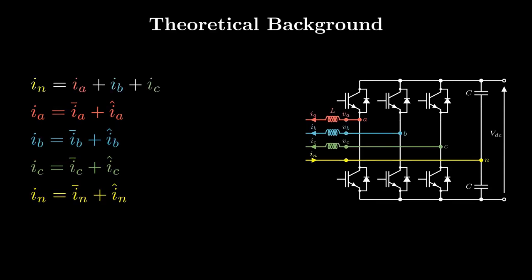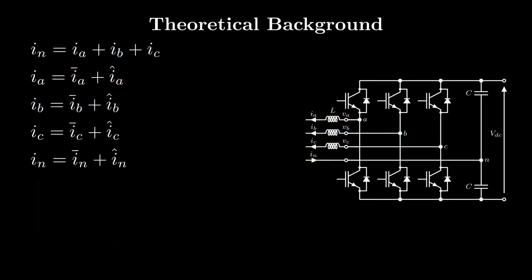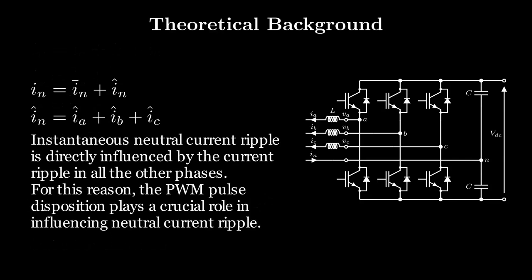The neutral current is given by the sum of phase currents, and any of these currents can be split into two parts. The first one is the AC component, having sinusoidal waveform. The second one is the switching current ripple caused by PWM high-frequency component. Therefore, neutral current ripple can be seen as the instance-by-instance summation of each phase current ripple.